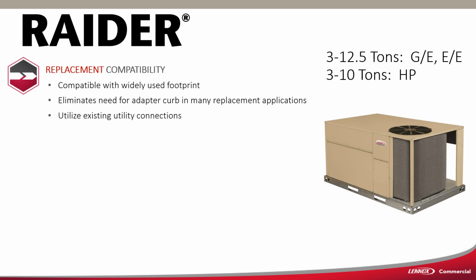It's compatible with a widely used footprint throughout the industry. In fact, this footprint was originally on the 50 and 48 series carrier package units. They go back 30 years. A lot of manufacturers tried to copy that footprint so they could replace them, which means there's a bunch of these units out there with that same footprint. You do not need an adapter curb, and all the utilities are in existing places. So if you've got a gas unit, the gas and the electrical that are coming through the curb will come out in the right place.